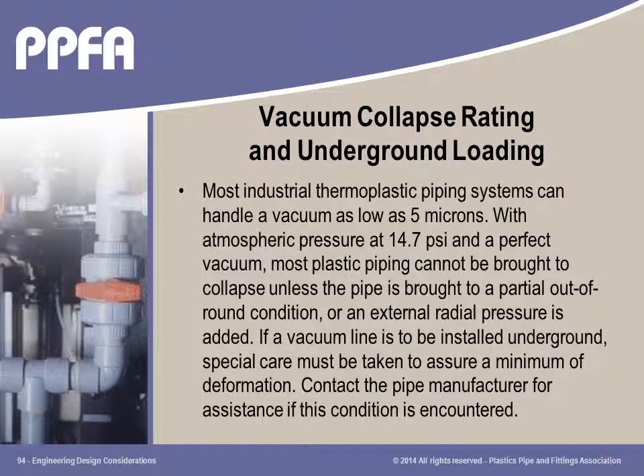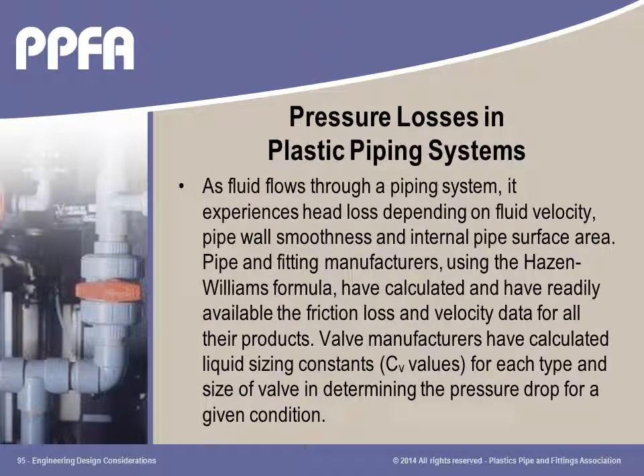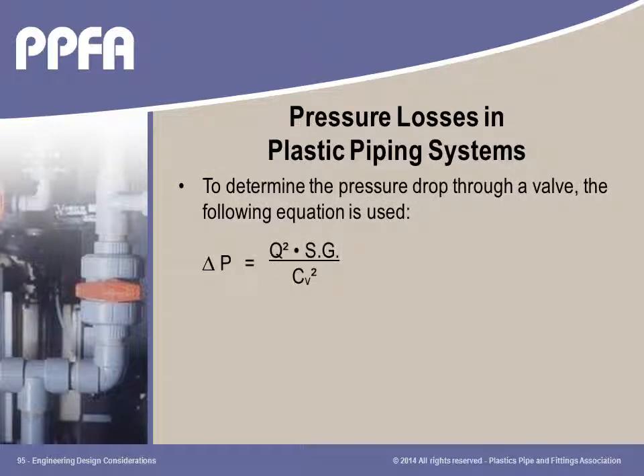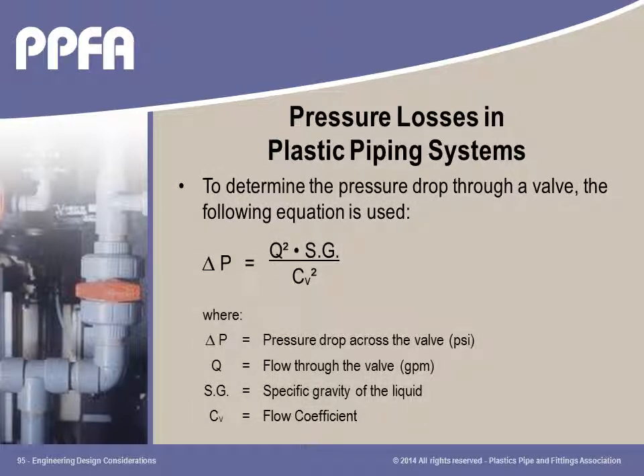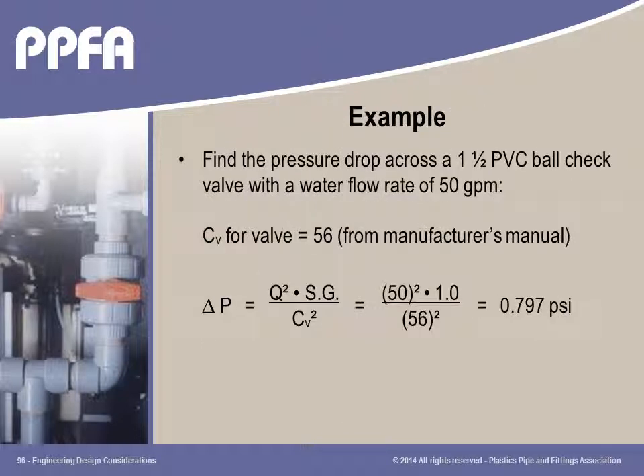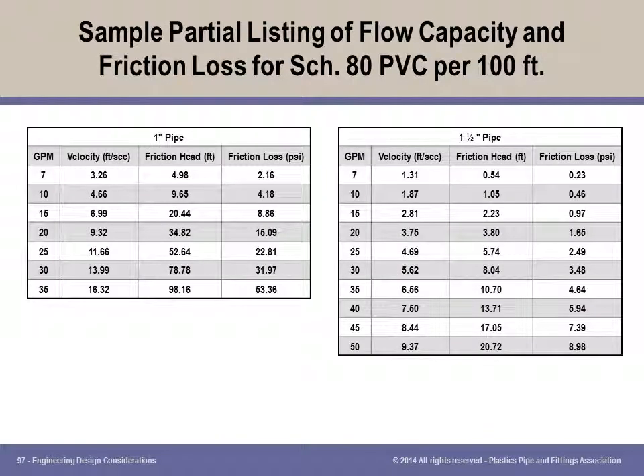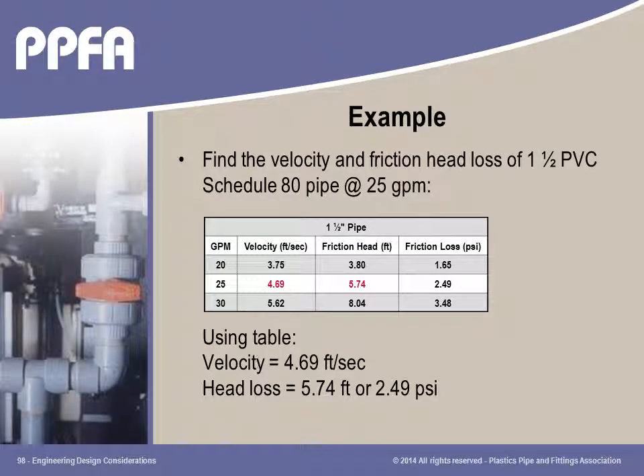In almost all thermoplastic piping applications, collapsing of pipe walls from a vacuum or negative pressure is not a major consideration. Almost all thermoplastic piping products have had their pressure loss calculated and listed using the Hazen and Williams formula. Friction losses are usually lower with plastics than other piping products. The example shown uses the formula to calculate the friction loss through a valve. Knowing the pipe diameter and flow rate, the velocity and friction loss can be calculated. Friction loss tables are available for most pressure-rated thermoplastic pipe, fittings, and valves. In the example shown, it is a simple task to determine the friction loss in feet or psi.